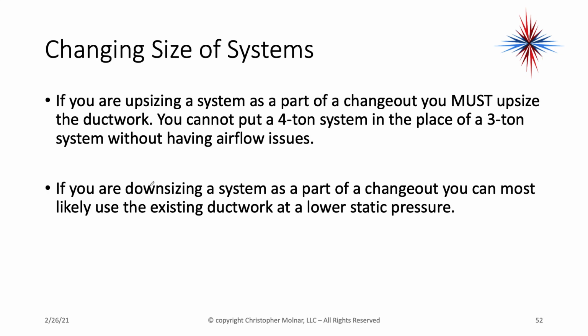For installs and changeouts, if you're upsizing a system that is part of a changeout, you must upsize the ductwork. You cannot put a 4-ton system in the place of a 3-ton system without having airflow issues. If you're downsizing a system as a part of a changeout, you can most likely use the existing ductwork at a lower static pressure.